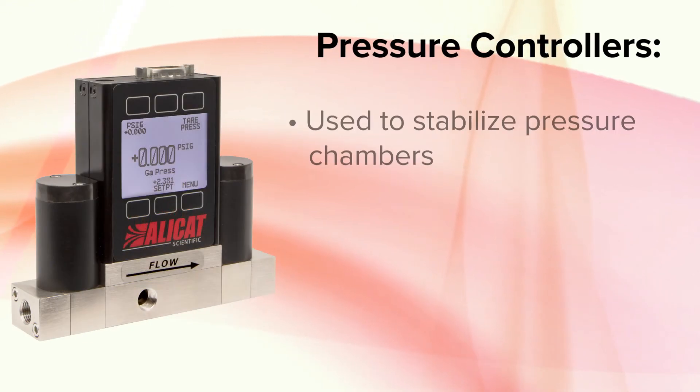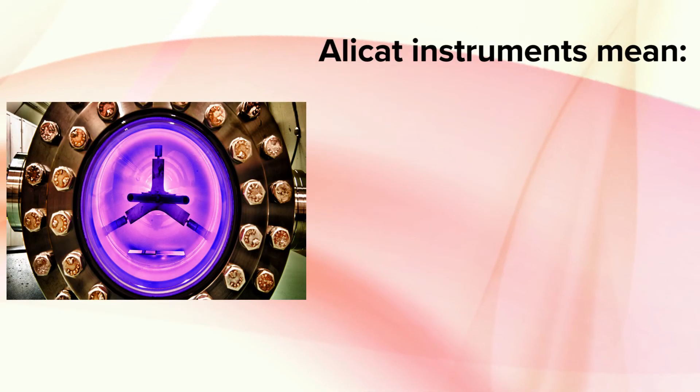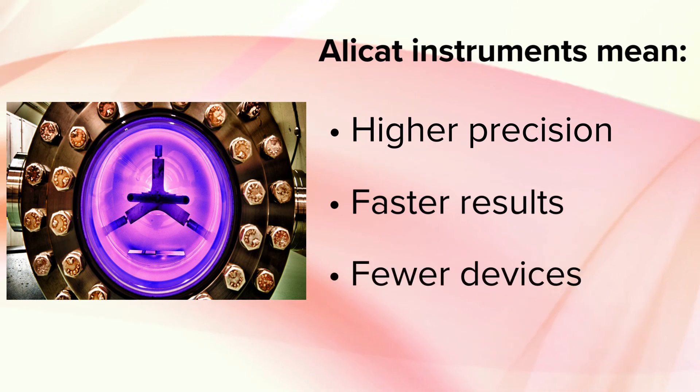Alicat pressure controllers stabilize vacuum levels and can eliminate the need for external vacuum gauges. By using Alicat's scientific instruments, manufacturers are able to improve precision and speed in several vacuum deposition processes with fewer devices than ever before.